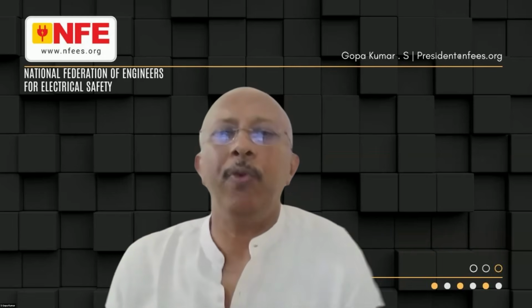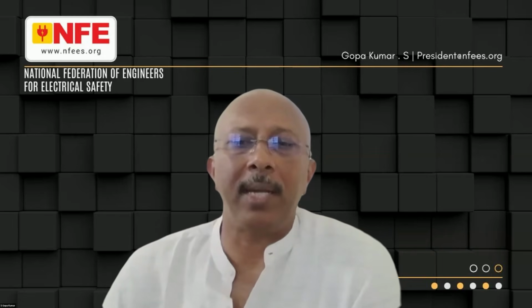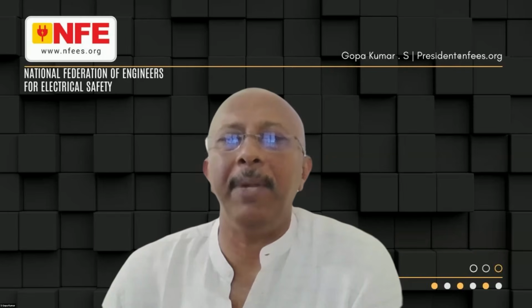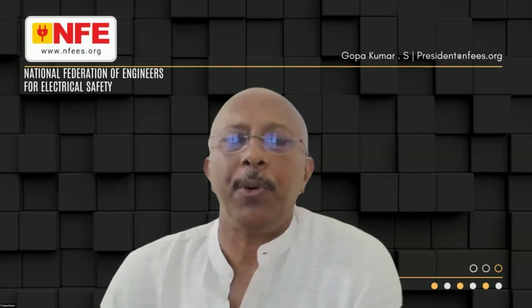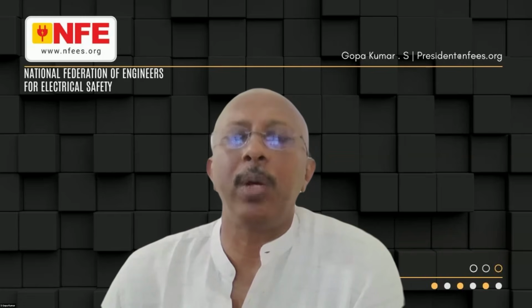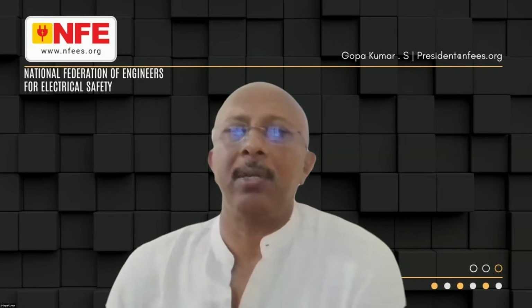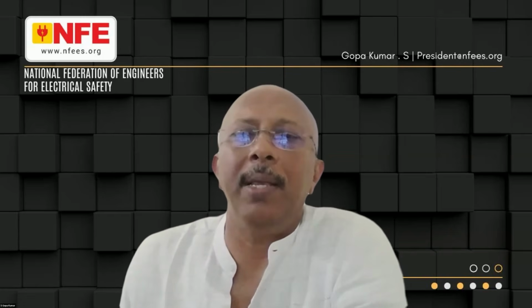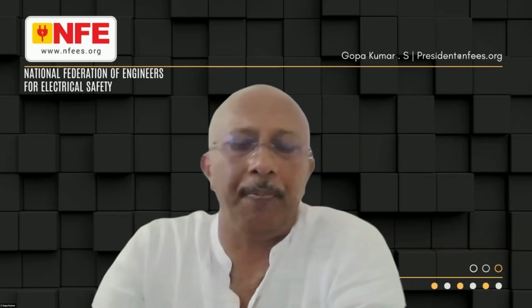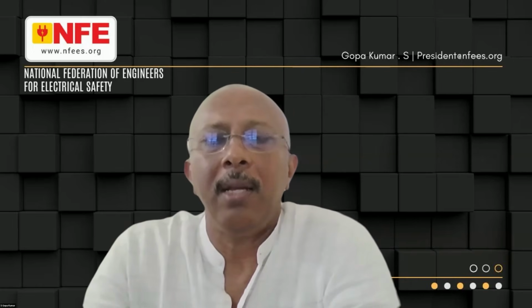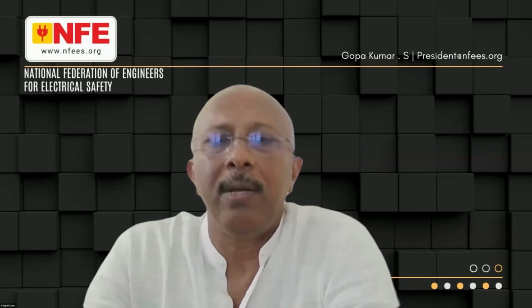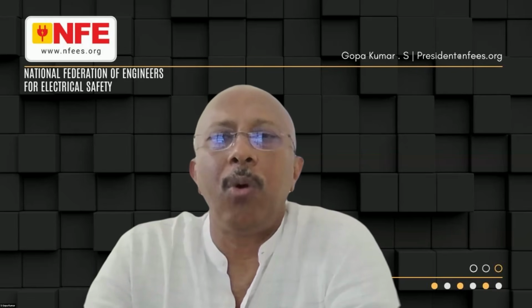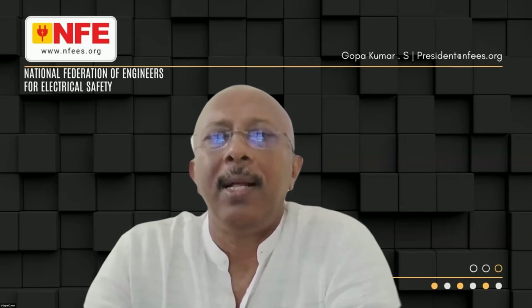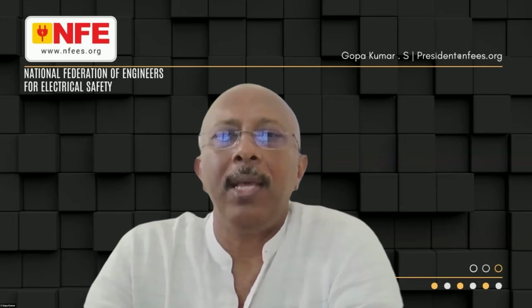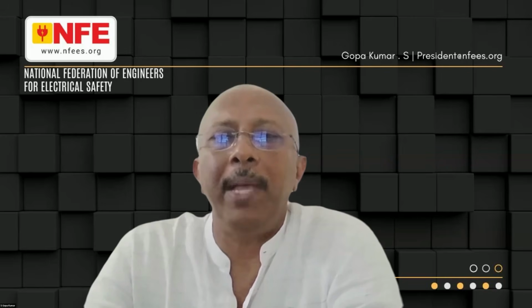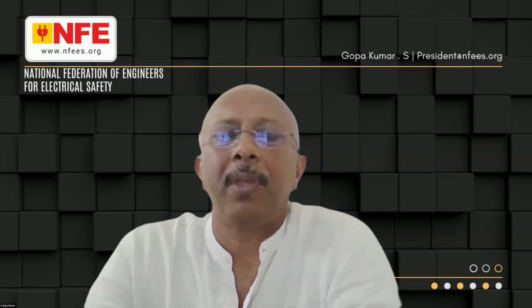The most modern way of this functional earthing is called as mesh BN, mesh bonding network. That means protective and functional earthing are together, which offers very high reliability. Now, regarding this 1 volt, there are biomedical equipment working with 230 or 400 volt single phase or 3 phase. They have a reference plane for the electronics, and the reference plane is based on the neutral potential.